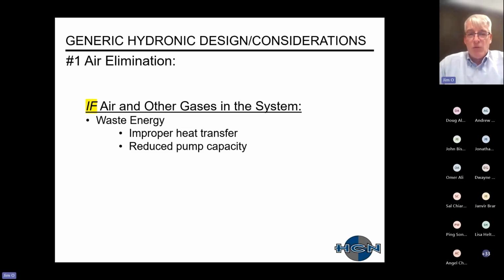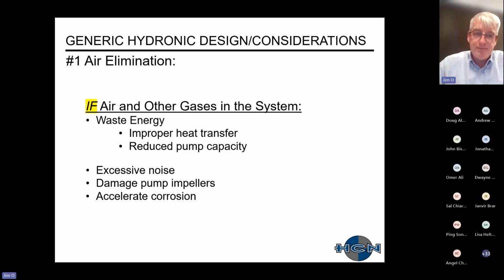So because it's not water, it's not transferring energy from the chiller to your fan coil to your system. With the addition of air and other gases in your system, you'll end up wasting energy due to improper heat transfer. And then once again, from a pumping standpoint, from a pumping capacity, you have air mixed in with your water. Obviously it makes sense that you're reducing your pump capacity.